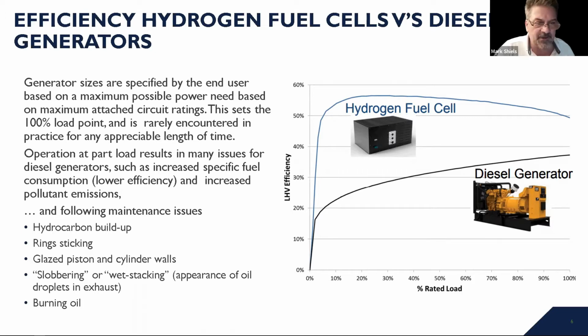And it's simply because when you size a diesel generator, or when you figure out which one you need, the DG size or the generator size is normally specified in accordance with what you think is the maximum power required. And that's normally calculated based on what your attached circuits or individual loads are likely to be. So this sets the 100% load point, which is very rarely encountered in practice. Or even if it is, it's never really running at full load for any appreciable amount of time.